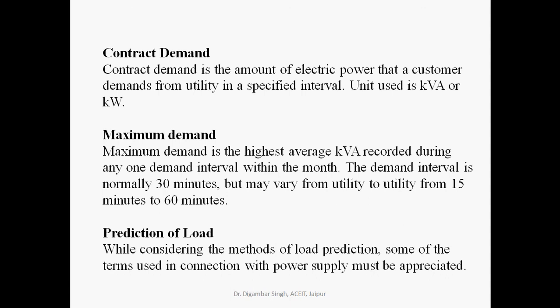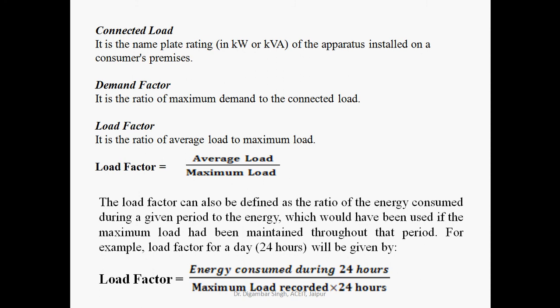Prediction of load involves several key terms used in connection with power supply. These include connected load, demand factor, and load factor. Connected load is the nameplate rating — the kilowatt or kVA rating of apparatus installed on a customer's premises.